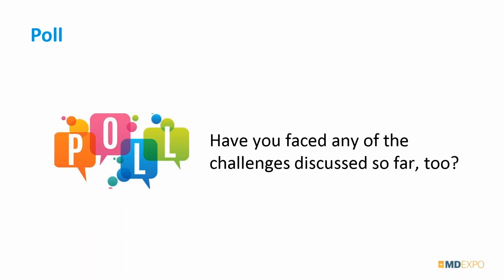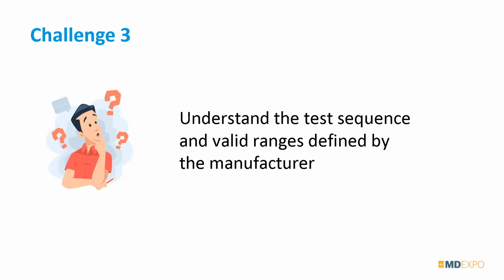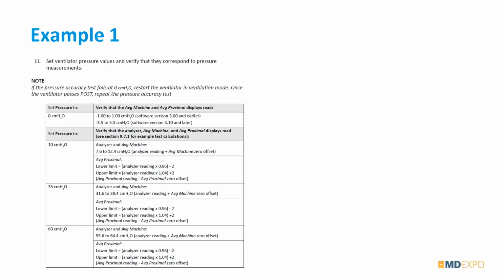All right. Yeah, so the last one we want to discuss with you is understanding the sequence and valid ranges defined by the manufacturer. So what do we mean with that? Sometimes you will see examples like this where it's quite a bit of a sequence they tell you to test. So first, there's something you have to do at 0 pressure, and then typically you have to measure different pressure levels, for example, and compare it to what you measure on the gas flow analyzer, right? In an ideal case, it would say, okay, set the pressure to 10, and then your gas flow analyzer should be between 9 and 11. Right, that would be an easy case.